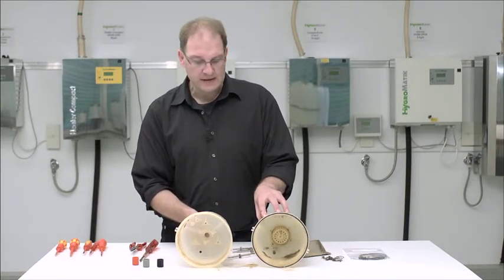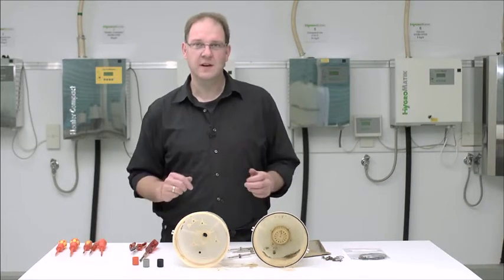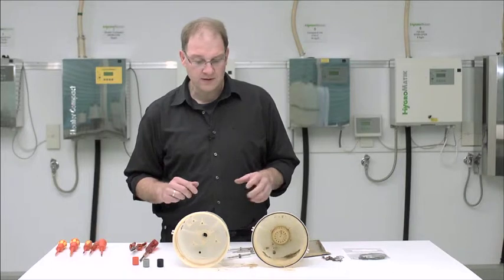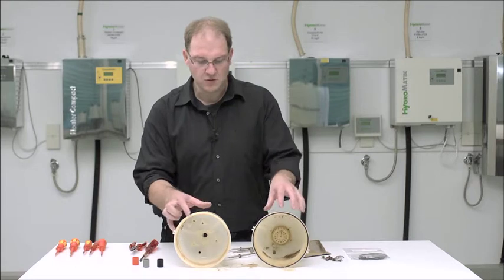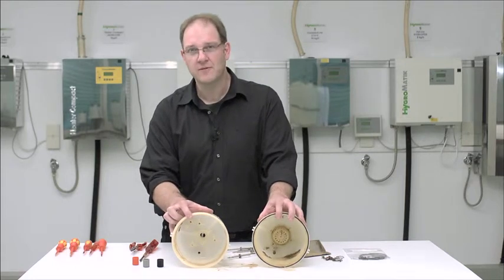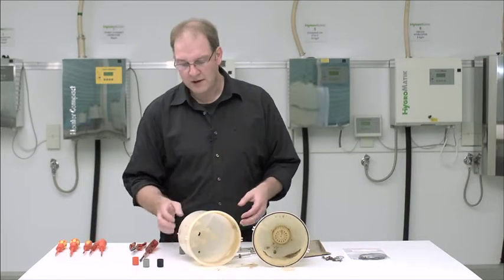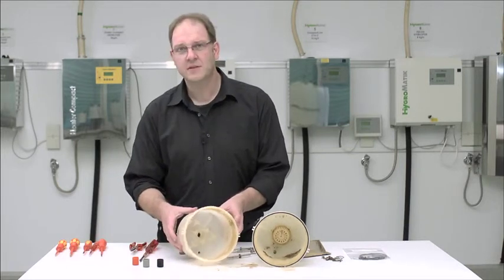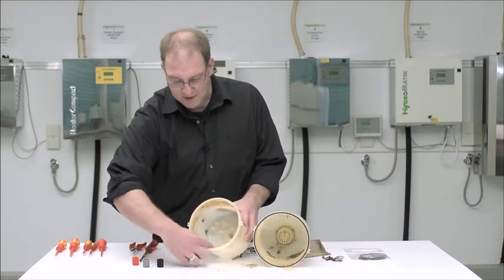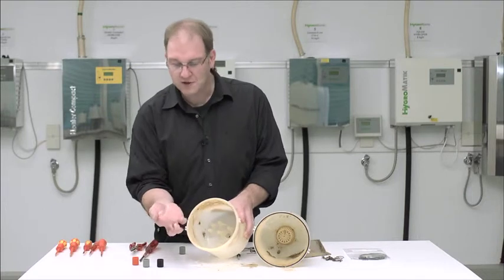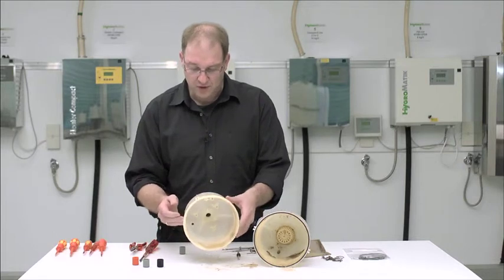When handling these electrode humidifiers, please don't use cleaning agents, because the principle of these electrode humidifiers is to send an electric current through the water, and it would be disruptive if we had any chemicals in the water, because with them the generation of such a current would be severely disrupted. Well, to clean the electrodes, I would now use a putty knife, a knife or other, and really just simply scratch down upon the surface. We currently have here a kind of lime scale formation. This I can get rid of quite easily with my fingers. It is, however, in its present degree of development not at all bothersome.